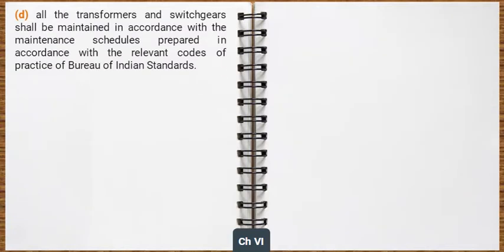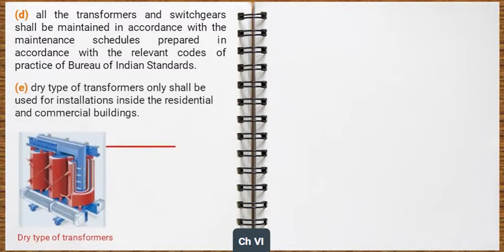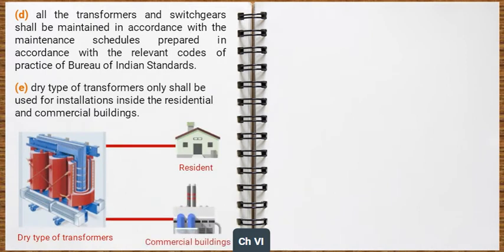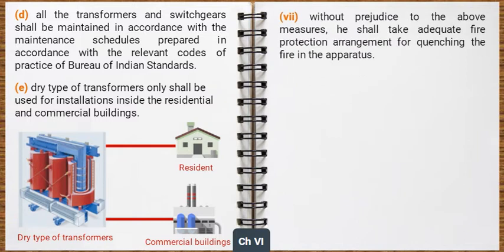All the transformers and switchgears shall be maintained in accordance with the maintenance schedules prepared in accordance with the relevant codes of practice of Bureau of Indian Standards. Dry type transformers only shall be used for installations inside residential and commercial buildings. Without prejudice to the above measures, he shall take adequate fire protection arrangement for quenching the fire in the apparatus.